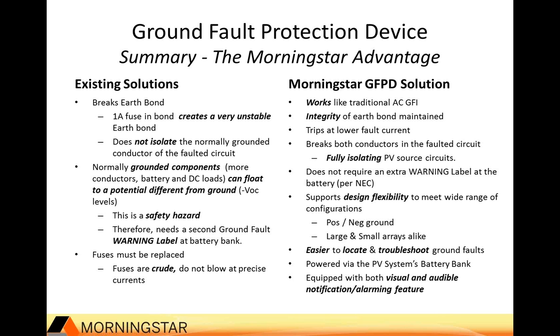Morningstar's ground fault protection solution works like a traditional AC ground fault interrupt. Okay, it maintains the integrity of the earth bond at all times. It detects an imbalance in current flow. We trip at a much lower fault current. When we do trip, we break both conductors, so both the positive and negative are disconnected, so it completely isolates the system. For that reason, we don't require any kind of warning at the battery because both the positive and negative are tripped, so it's completely isolated. It's usable in both positive and negative ground systems, and even for larger arrays. You only need one ground fault protection device, even if you're using many of our charge controllers. It also makes it easier to locate and troubleshoot the ground fault.